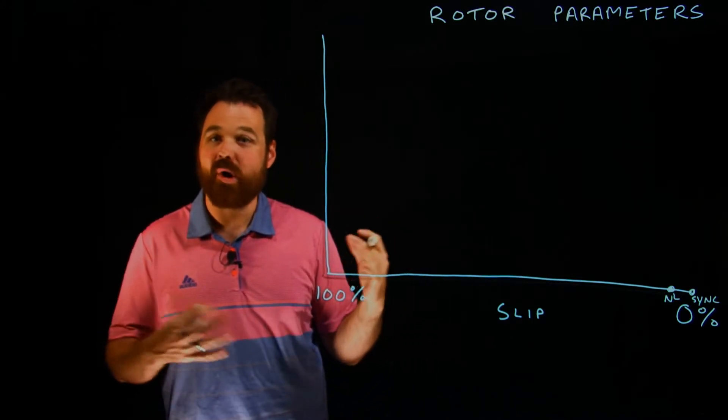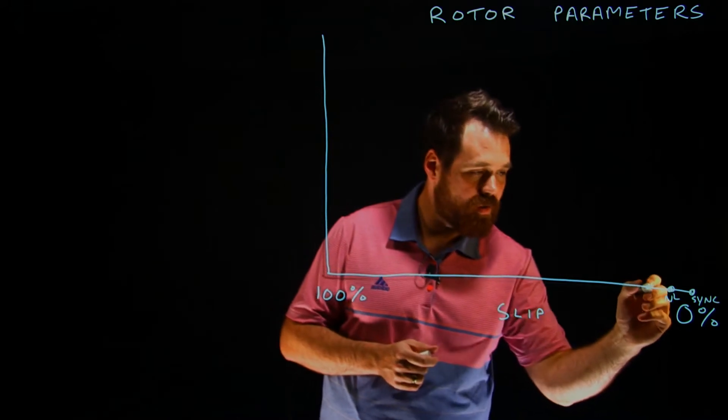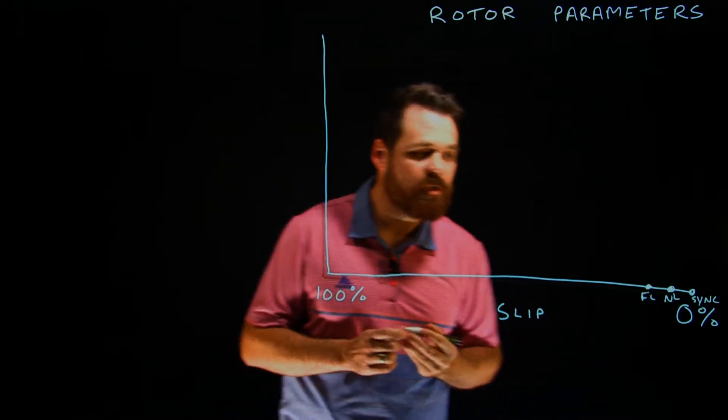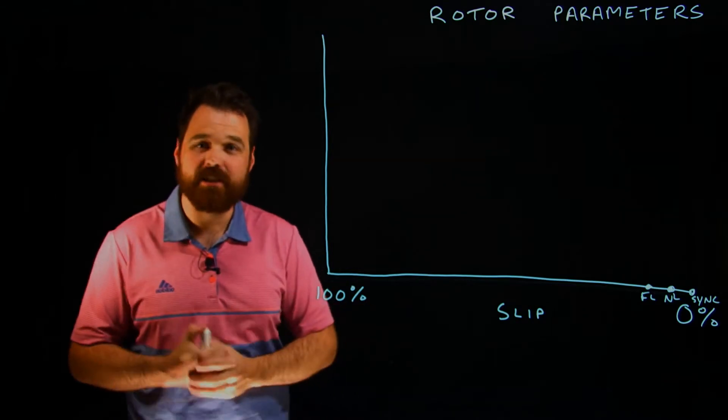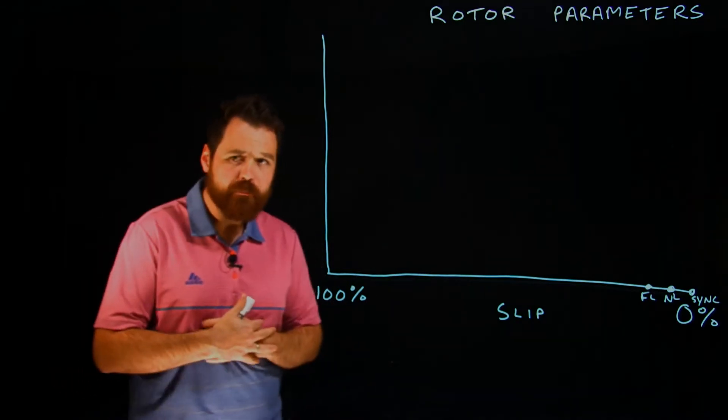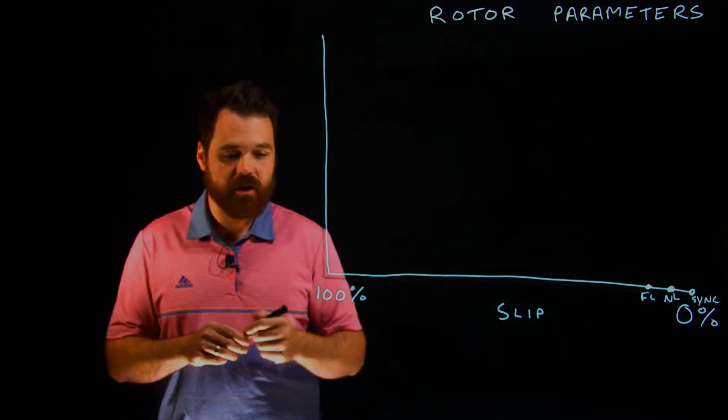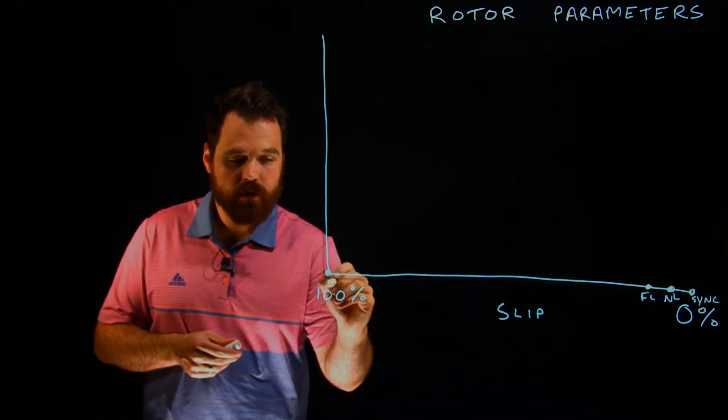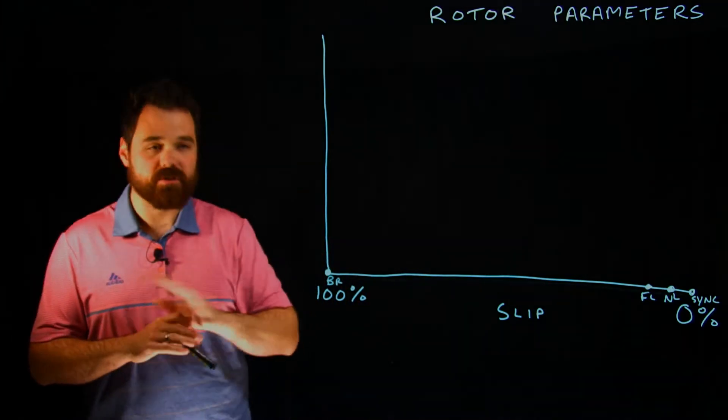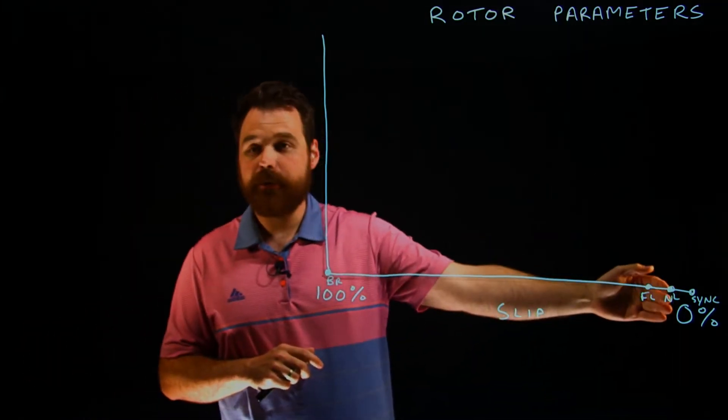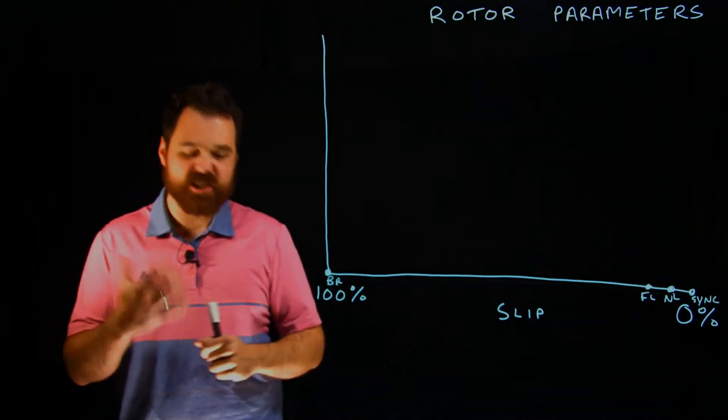And then we would have our full load speed pretty close there as well. We usually talk about two to 8% slip for that full load. So we'll kind of talk about how that rotor is from what we would call down here a blocked rotor, meaning it is stopped. There's 100% slip. The synchronous speed is whatever it is. Rotor is not spinning at all.